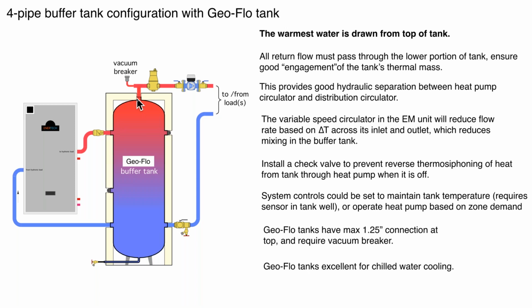Now, one of the things that is important with this tank is a vacuum breaker, and that actually is supplied with the tank. The reason a vacuum breaker is there: if you have a system with hot water in it, and the tank is allowed to cool down, or the tank goes into a chilled water cooling mode, that water is going to shrink in the entire system. And the diaphragm in the expansion tank may bottom out against the shell of the tank. At that point, remember, water is an incompressible fluid. That water is actually going to be pulling inward on that polypropylene liner. And to prevent any damage in the tank, that vacuum breaker needs to be installed. It's a very simple little component. I'm just showing it teed in up here at the top.